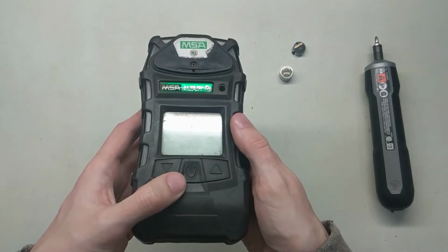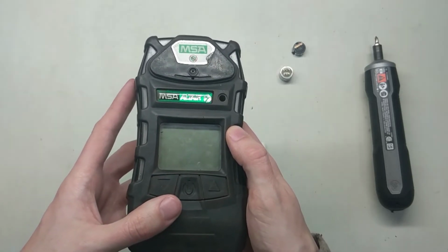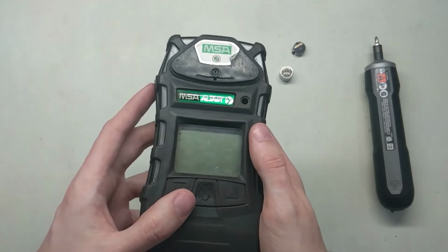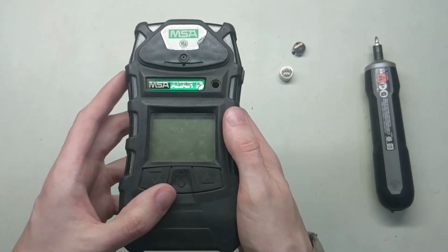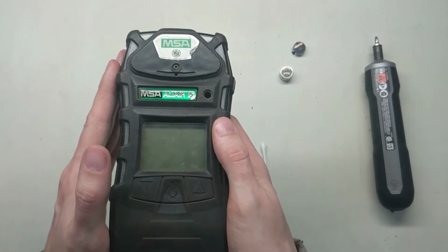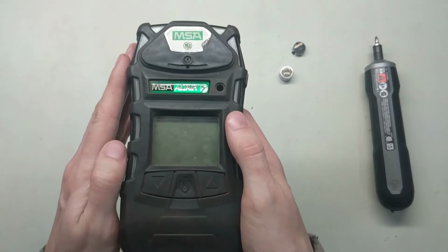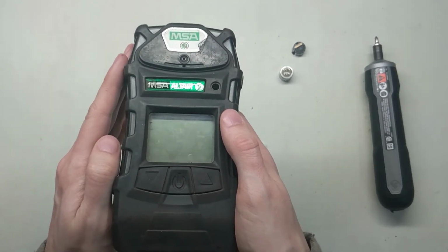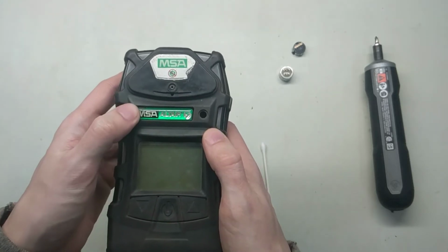One other thing you want to do when installing the sensors is always record the serial numbers and date codes, because if they die or anything along those lines, you know you've got a warranty on them. For the 5, the warranty is 2 years per sensor. If you have a 5X unit, those are usually 3 years per sensor, since the sensor technology is a little different.